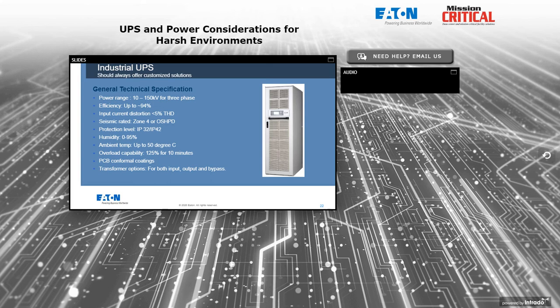The presence of water inside a UPS is always going to be a problem. You can conformally coat the boards and put drip shields over the top of the machine or the front of the machine. But in general, humidity that condenses inside a UPS, no matter how it's designed, is going to be a potential for what could be a catastrophic failure. So we want to try to keep that humidity in a non-condensing range. Otherwise, the UPS should be positioned as a box within a box to where the interior of the box can be controlled for humidity. Ambient temperature up to 50 degrees C, some requirements even higher.